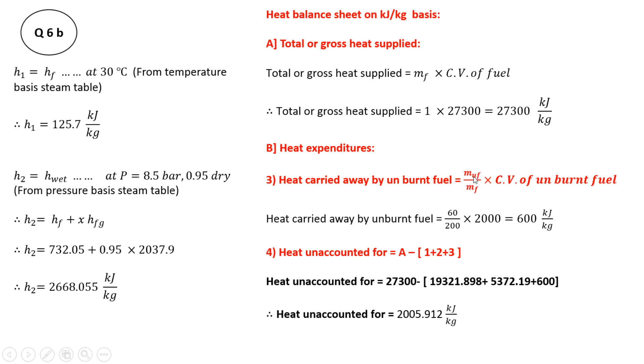Heat carried away by unburned fuel: since our heat balance sheet is on a per kg of fuel basis, we divide mass of unburned fuel by mass of fuel and multiply by its calorific value: (60 / 200) × 2000 = 600 kJ/kg. Finally, the unaccounted heat equals total heat supplied minus the three calculated parts: 27300 − 19321.898 − 5372.19 − 600 = 2005.912 kJ/kg. Now we formulate the heat balance sheet.